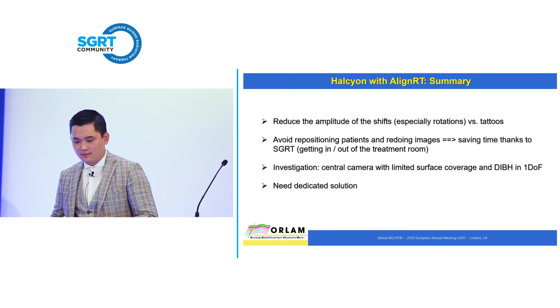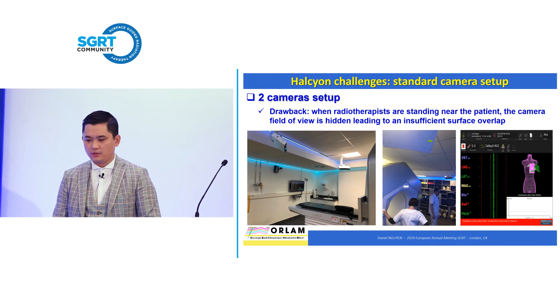Historically, when VisionRT decided to install our solution on Halcyon, they decided to install only 2 cameras. But with this setup, we have a drawback. When therapists are standing near the patient, the camera field of view is hidden, leading to an insufficient surface overlap. So after some discussion with VisionRT, they finally decided to install 3 cameras, like our TrueBeam installation. And with three cameras, we don't have more occlusion issues, but the cameras are still calibrated to the external lasers of the bore. And we don't have the tracking inside the bore.